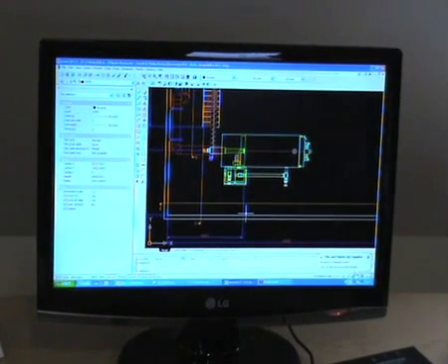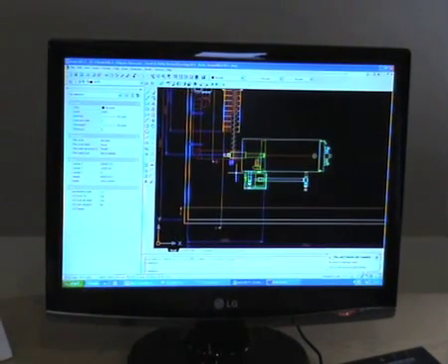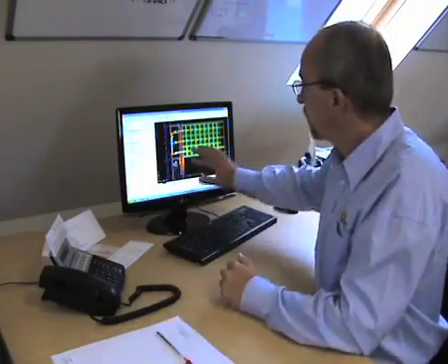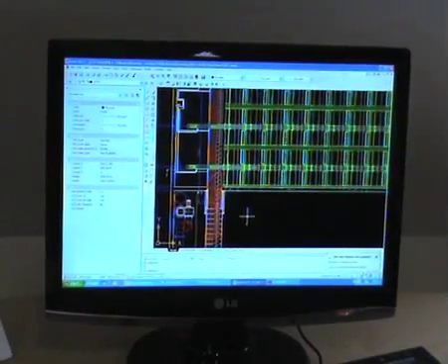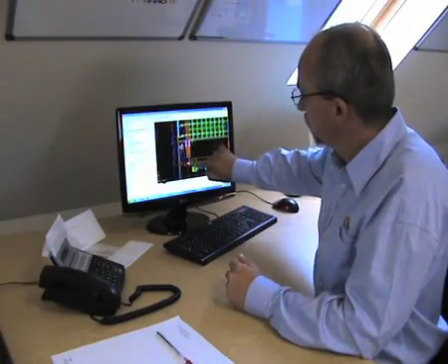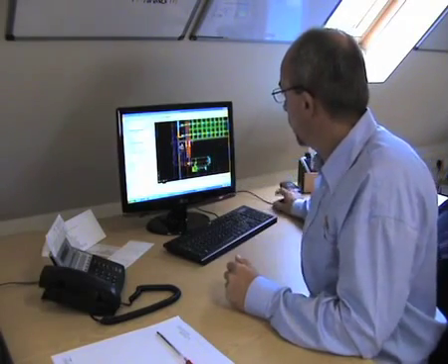You can see a drawing on screen there. The blue entity there representing a 1.6 megawatt boiler, which is fed by what we call a walking floor, which is a system of teeth that move backwards and forwards and pull wood chip into a feed auger, which is set here, that then falls into a rising auger that feeds it into the back of the boiler there. From there you have a system of pipework and a control philosophy that feeds that into the entities to be heated by means of a network mains system.